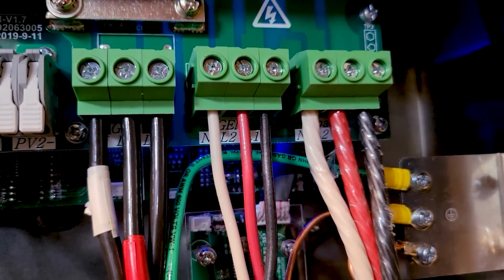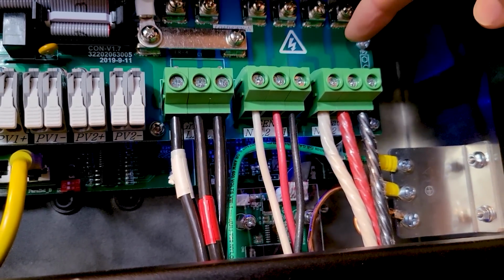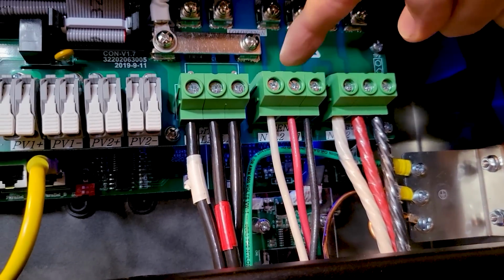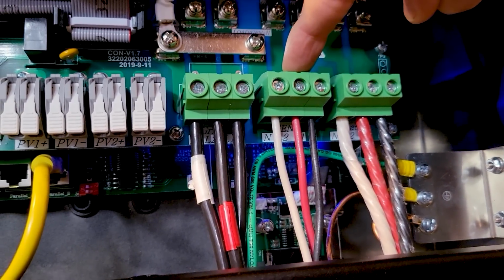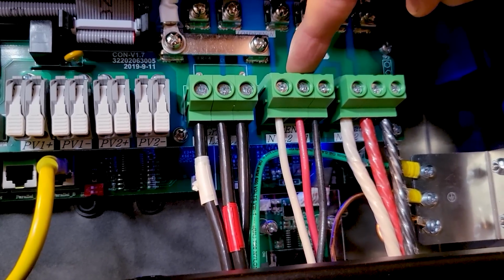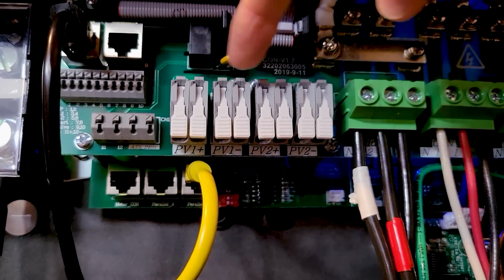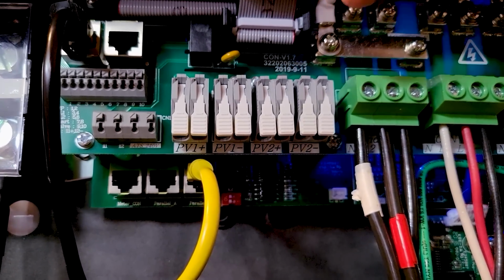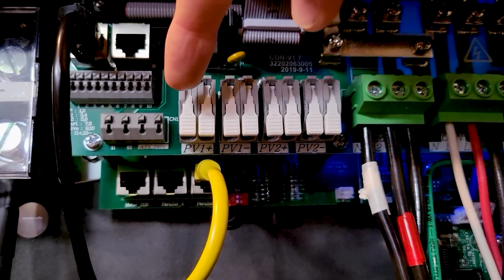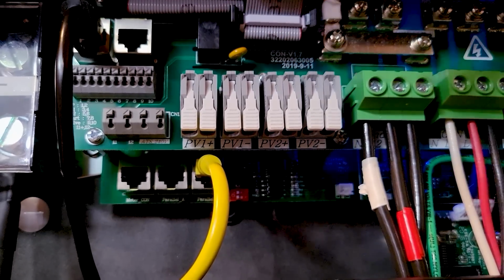And these are all your AC inputs and output. The grid input to this battery. We have the load output to the backed up loads panel. And this is a multi-function input or output port, which can either be generator, it can be AC coupled solar, or it can even be a smart load. So here we have the PV inputs. So if we had DC coupled solar going to this, you have 4 strings that you can connect in, each with 2 MPPTs total, and they're combined here.